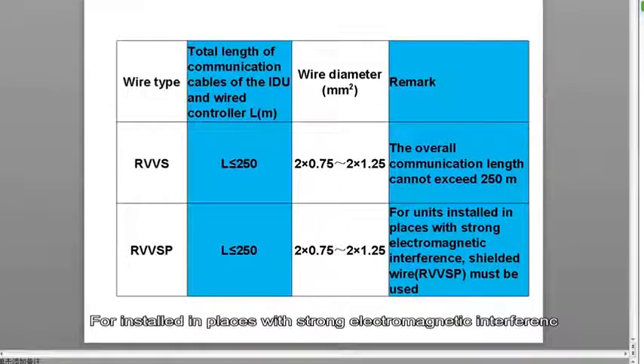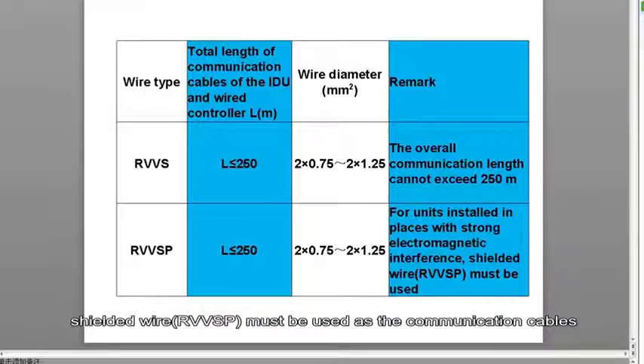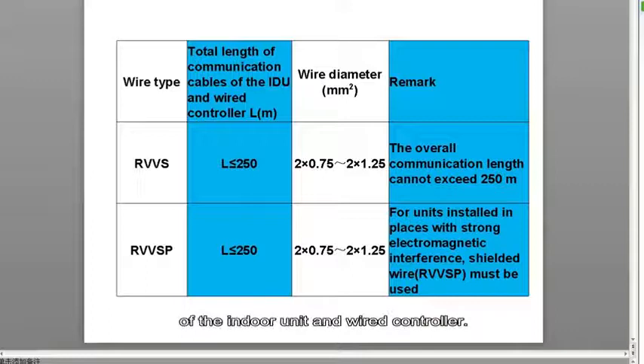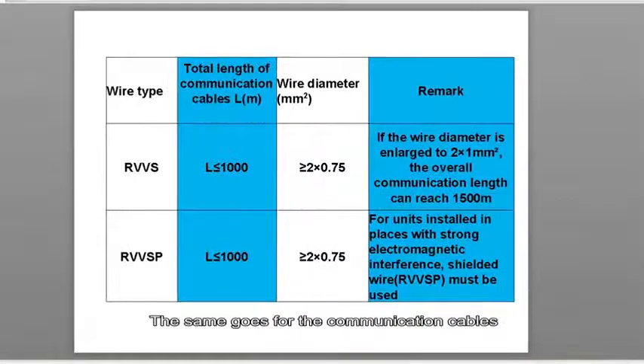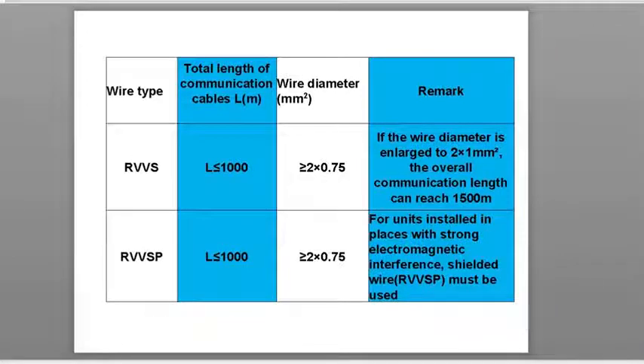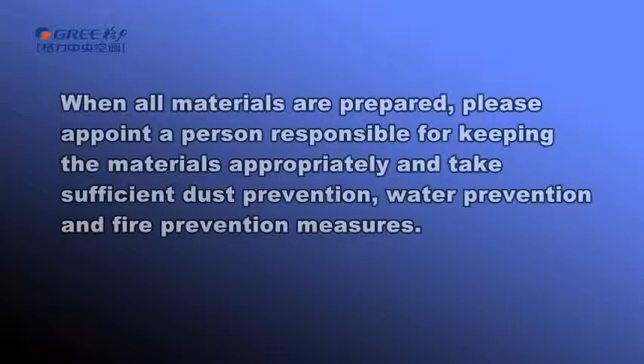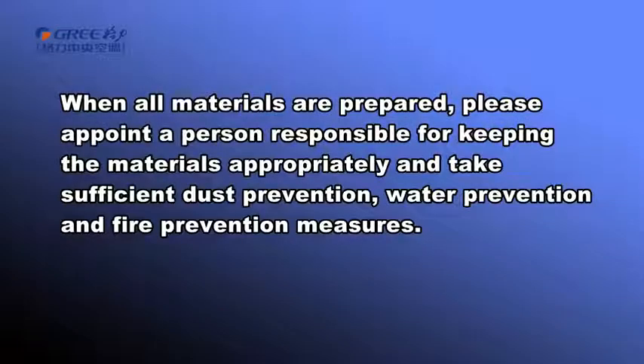For units installed in places with strong electromagnetic interference, shielded wire must be used as the communication cables of the indoor unit and wired controller. The same goes for communication cables between indoor units and between the indoor unit and outdoor unit. When all materials are prepared, please appoint a person responsible for keeping the materials appropriately to prevent them from dust, water, and fire.